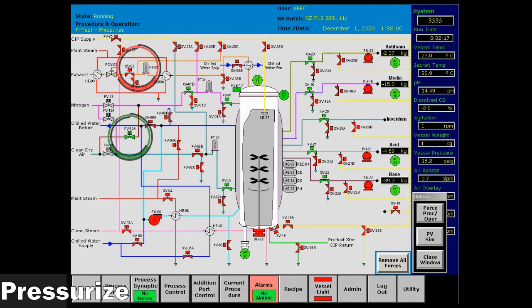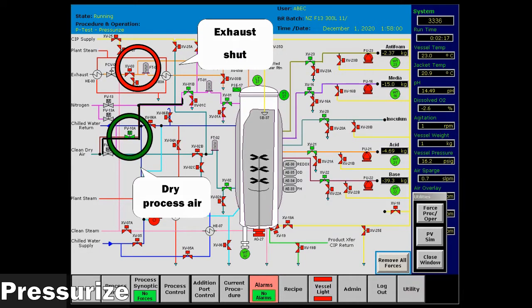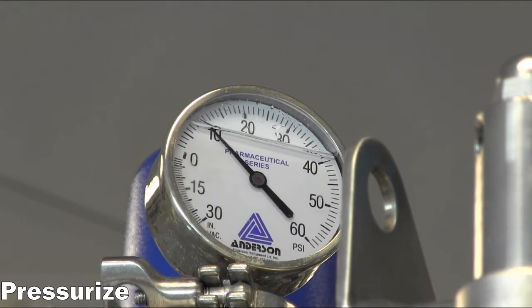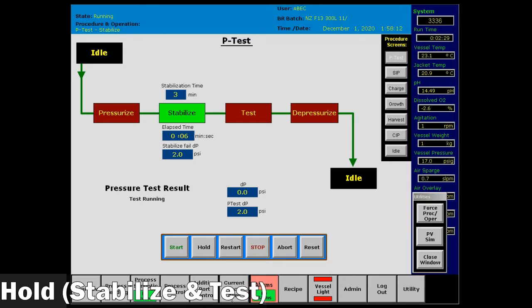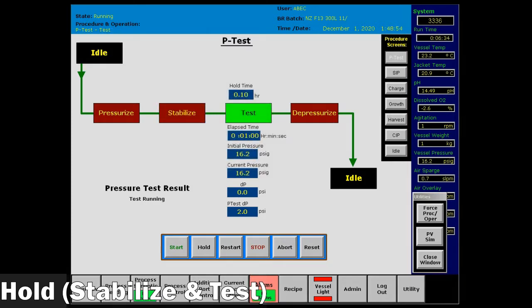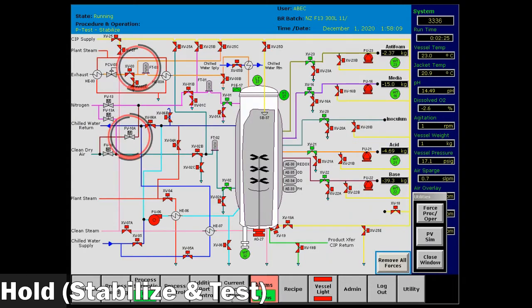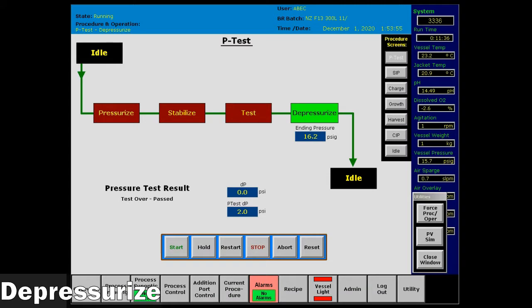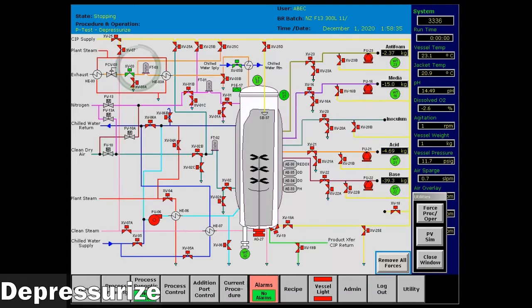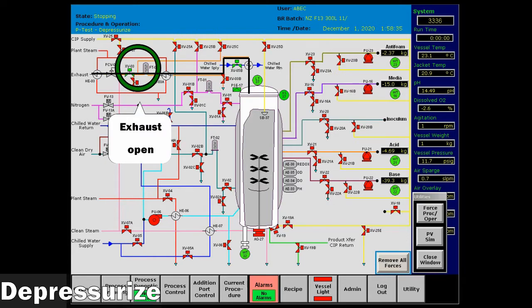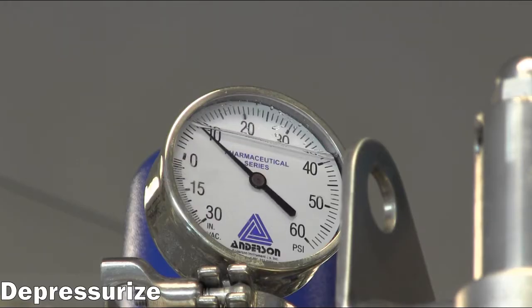Process air is pumped into the vessel until the pressure is about 16 psi. It will hold this pressure for 10 minutes to confirm there are no leaks. It will then depressurize safely. If the P-test passes, move on to the next step. If it fails, troubleshoot by checking valves, filter housings, tri-clamps, and rerun the P-test.